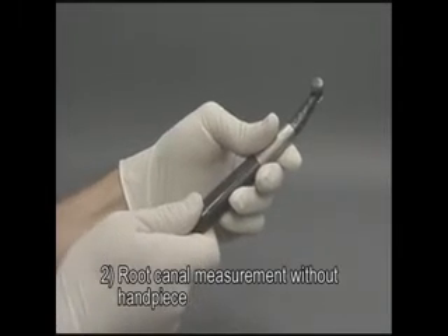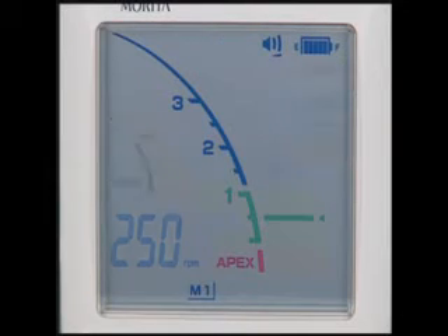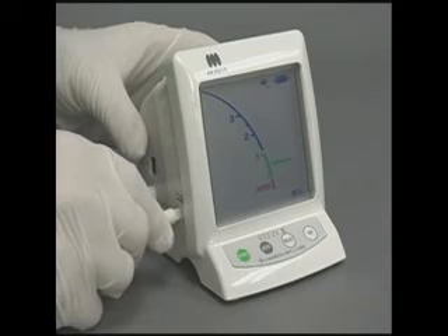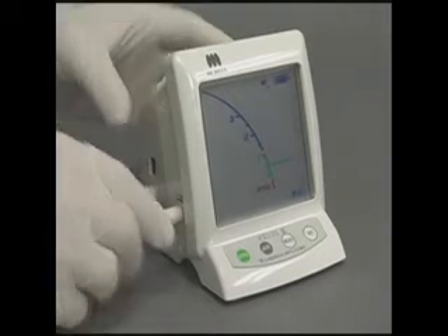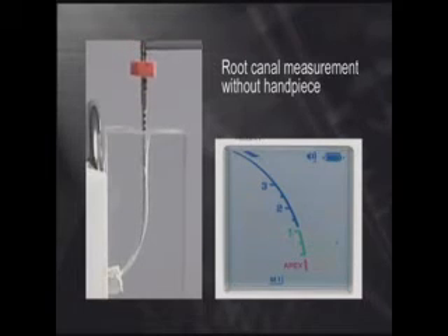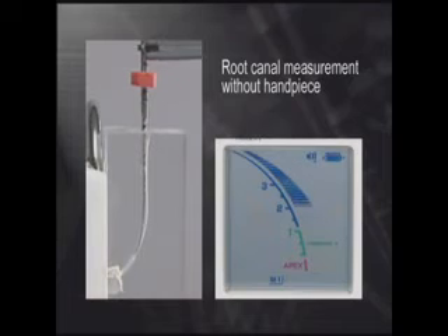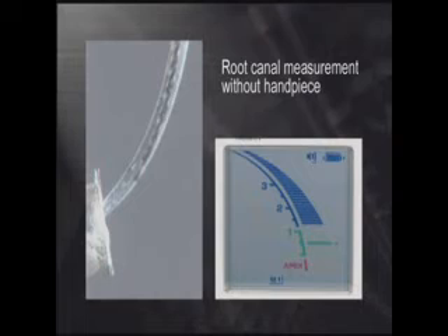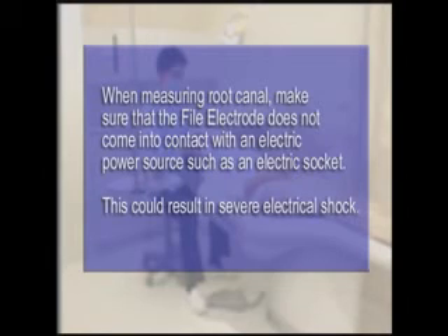Secondly, detach the micromotor from the handpiece cord. The unit automatically goes to the canal measurement mode. In this mode, follow the same instructions as previously mentioned when using the canal measurement module alone. When measuring the root canal, make sure the file electrode does not come into contact with an electric power source such as an electric socket. This could result in a severe electrical shock.